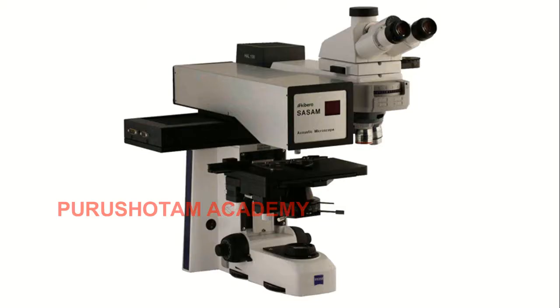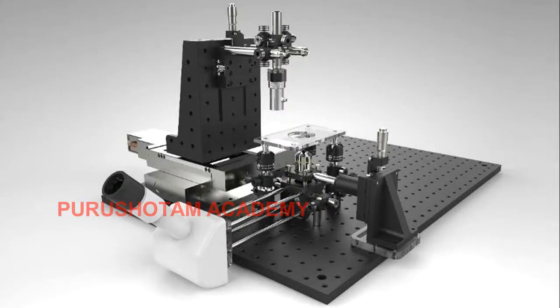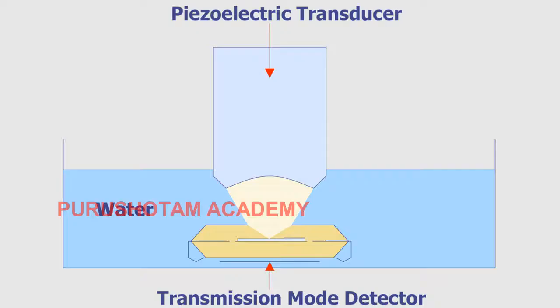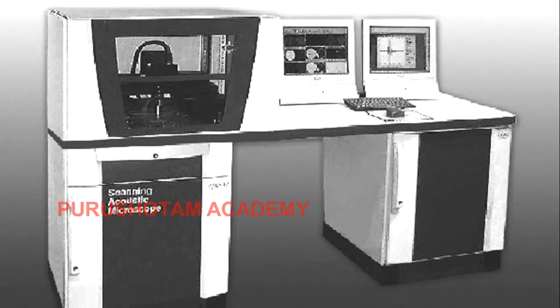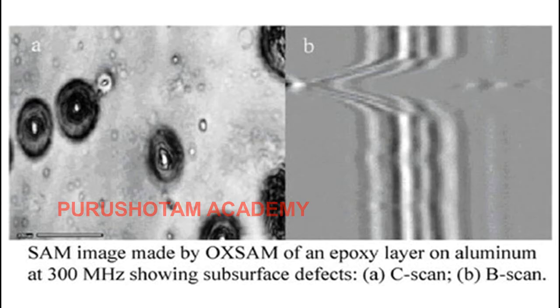Solid state systems allow the beam to be scanned across the specimen, enabling the non-destructive inspection of products such as integrated circuit packages. For these applications, 25 to 50 MHz transducers are employed to give real-time images that are amenable to automated computer analysis.